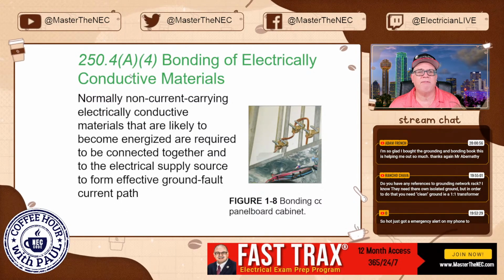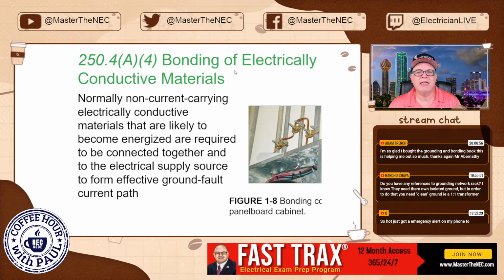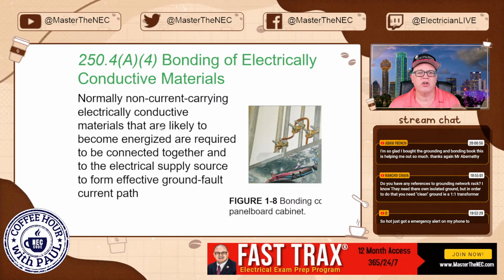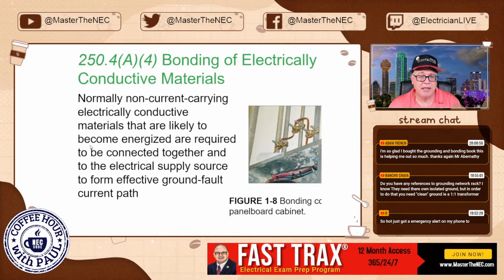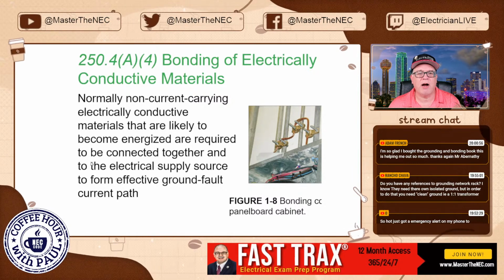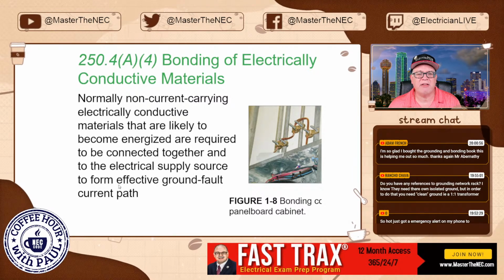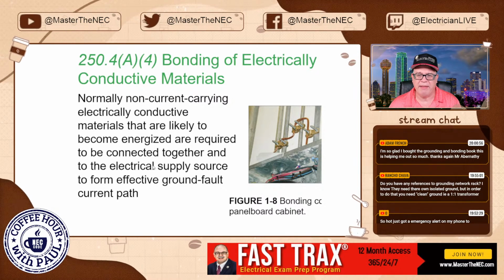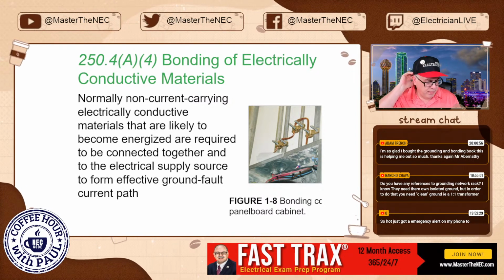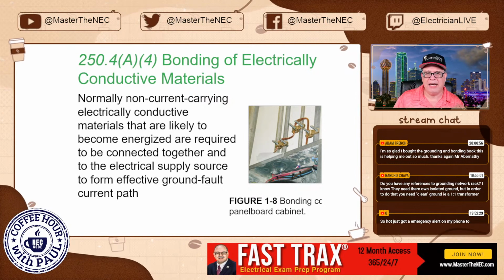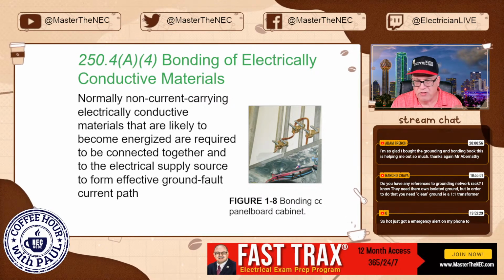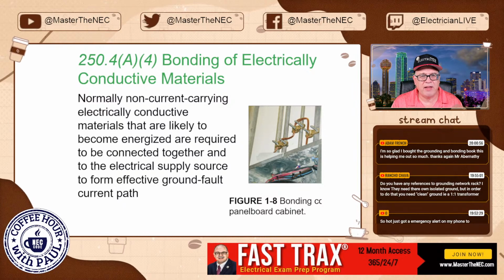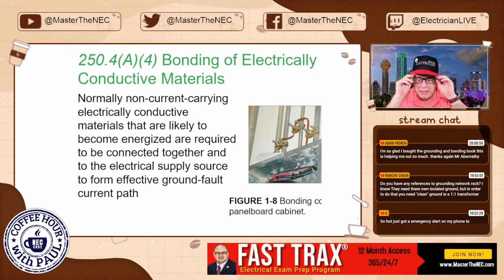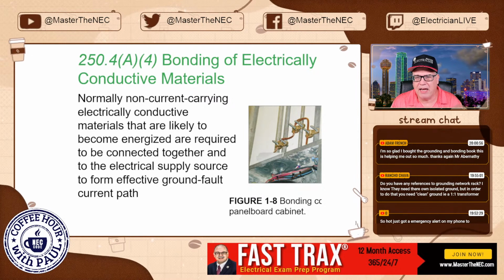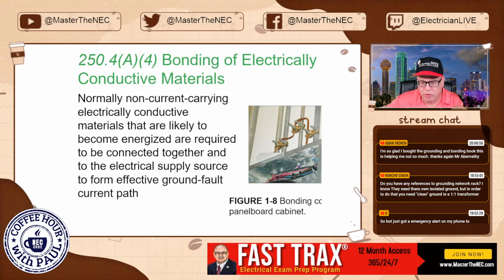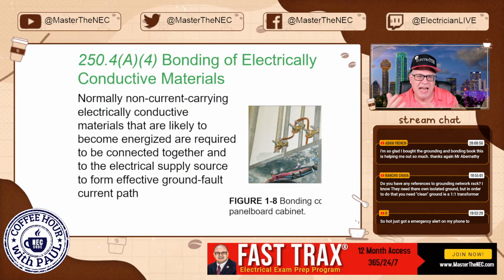All right, 250.4(A)(4), bonding of electrically conductive materials. Normally non-current-carrying conductive materials that are likely to become energized are required to be connected together and to an electrical supply source to form an effective ground-fault current path. This is an example where people ask me about gas lines. So you have 250.104 in the code, and they say, do I have to bond the gas line? Well, typically you don't have to bond the gas line. And we're not talking about CSST and the rules that you have for that, just gas line in general.